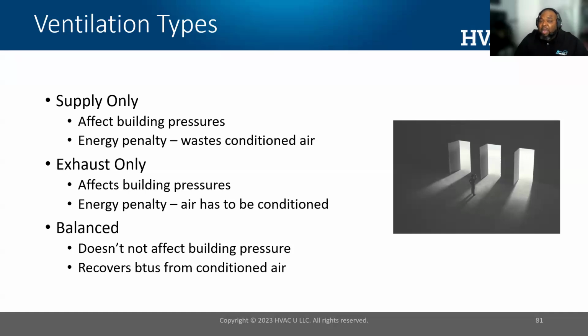Those two. Balanced ventilation really doesn't affect the building pressures. And when we talk about balanced from the standpoint of an ERV or HRV, they recover the BTUs that you paid your utility company, or a portion of them, and put them back into the house, and it reduces the energy penalty that you will incur by trying to ventilate.